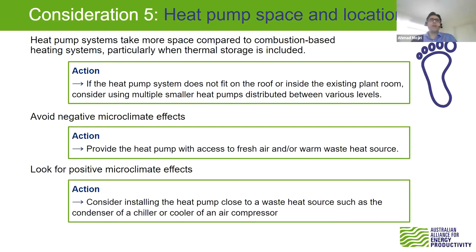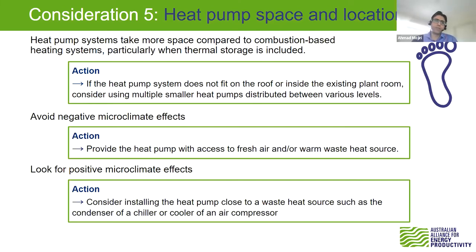On space requirements: if the heat pump doesn't fit in the existing plant room, one option is to divide a large heat pump into smaller ones distributed between various levels. However, you need to provide fresh outside air to the heat pump and avoid creating microclimates around it, where air temperature can drop and reduce COP. Ideally, deliver warm waste heat to the space. If there's any possibility to install the heat pump close to a waste heat source — such as heat rejected by a chiller — this will be easier and give higher COP.